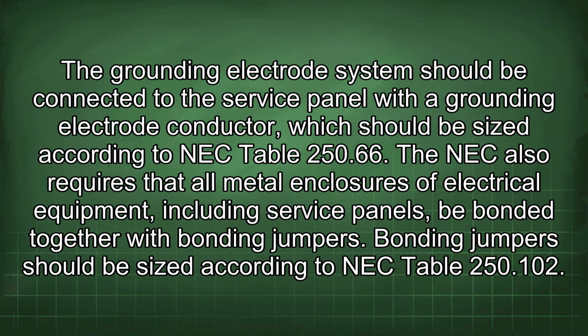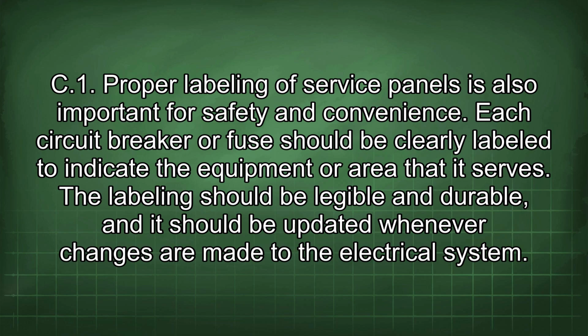The grounding electrode system should be connected to the service panel with a grounding electrode conductor, which should be sized according to NEC Table 250.66. The NEC also requires that all metal enclosures of electrical equipment, including service panels, be bonded together with bonding jumpers. Bonding jumpers should be sized according to NEC Table 250.102. Proper labeling of service panels is also important for safety and convenience.